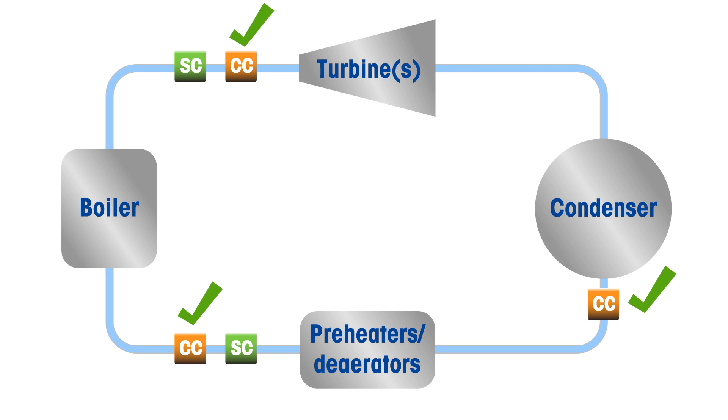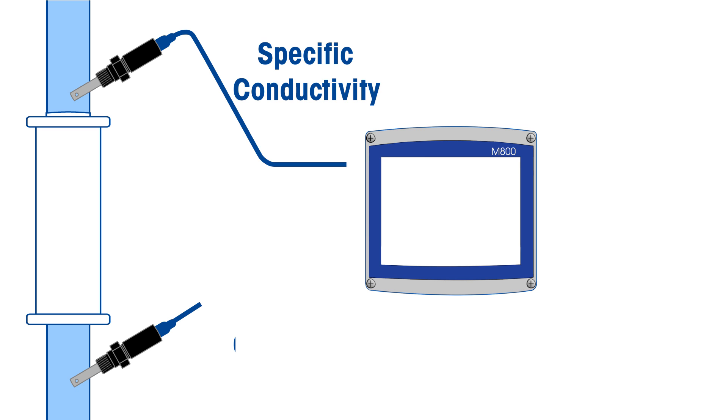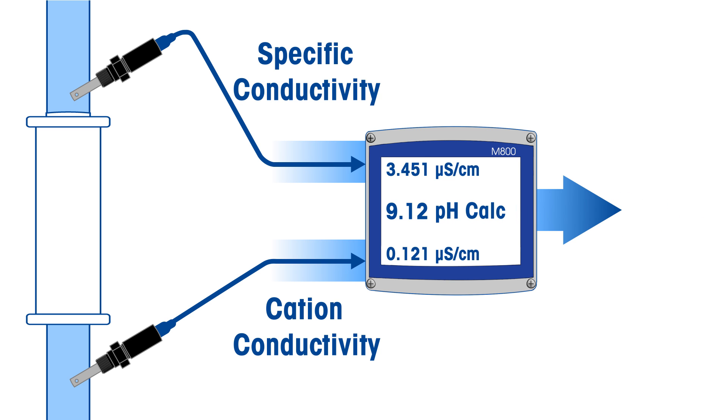However, correction for minor contaminants by measuring the cation conductivity of the sample is needed to provide accurate results. The specific and cation conductivity values are used in an industry-accepted calculation that provides the highest accurate conversion to pH.